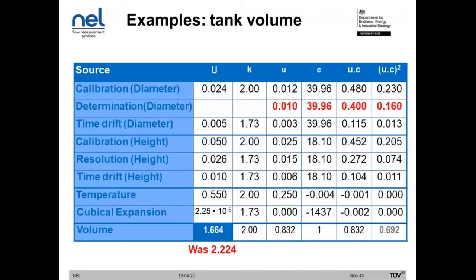So finally, by reducing the diameter determination uncertainty, we've got below 2% on the volumetric, the volume determination uncertainty. So we're now at 1.66%, and our job is done. So this is just a hypothetical example, but it gives you an idea of how the process works and how the uncertainty table or budget actually has real-world applications. If you're trying to improve the measurement system, then this gives you the information you need to spend the money in the appropriate places where it gets the best possible use.